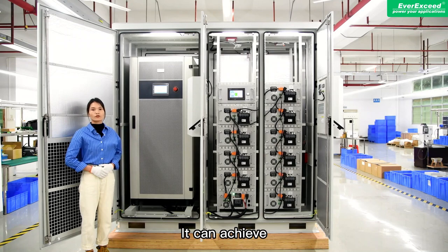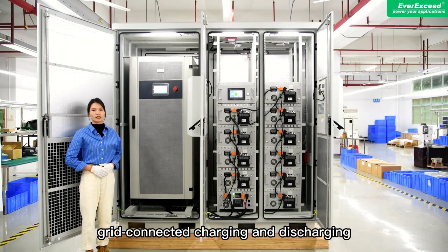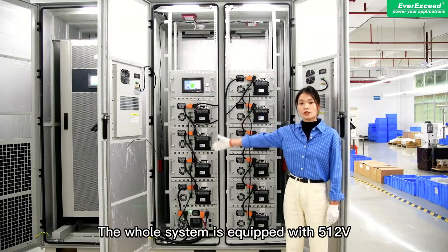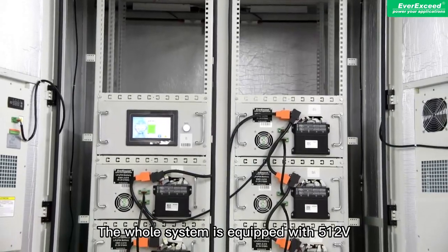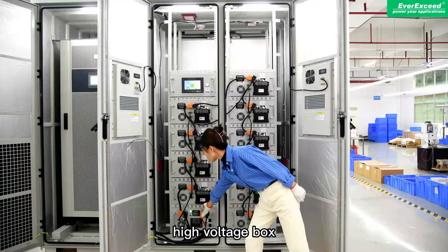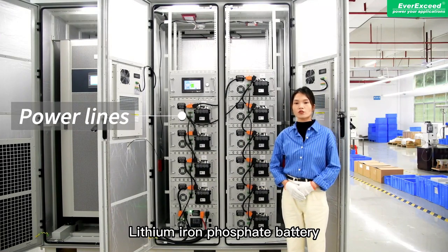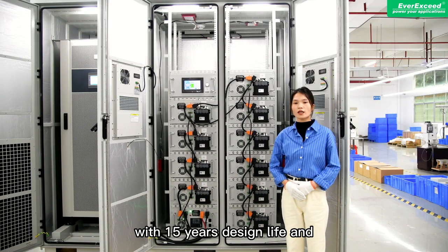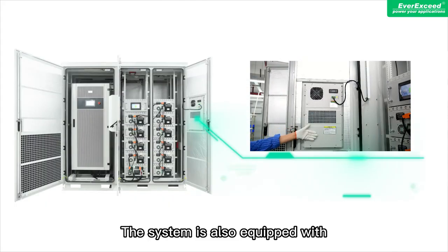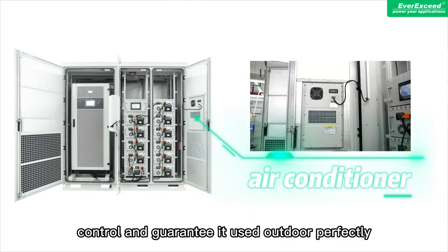This is the 30kW PCS. It can achieve bidirectional electric energy conversion. The inverter supports grid-connected charging and discharging and off-grid inverter function. The whole system is equipped with 512V, 210Ah lithium iron phosphate battery modules, a high-voltage box, and BMS system. The battery adopts grade-A lithium iron phosphate cells with 15 years design life, 6,000 cycle life, and 80% DOD. The system is also equipped with an intelligent air conditioner to achieve automatic temperature control and guarantee outdoor use.